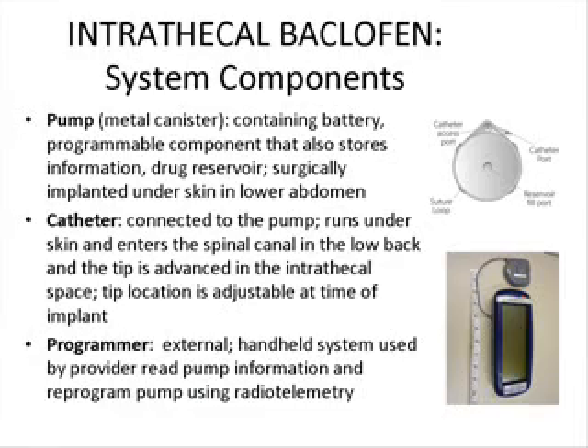So the third component is the programmer, which when I first learned about these came in a big suitcase, in a big system that you really couldn't carry by hand. And I think as with all technology, it's morphed into something that's handheld and smaller, so I'm waiting for the next generation of these to come through. But we use this system, and it's got a telemetry head, so it uses radio telemetry to actually read the pump information, or what we call interrogation of the pump, or analysis of the pump, and then to reprogram the pump to tell it what we want it to do. Okay.